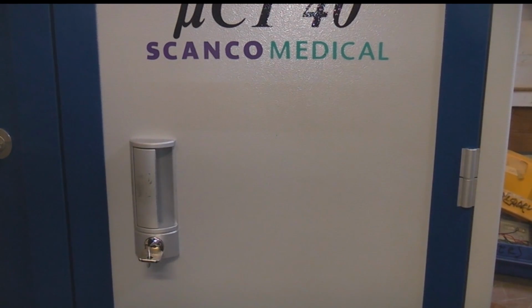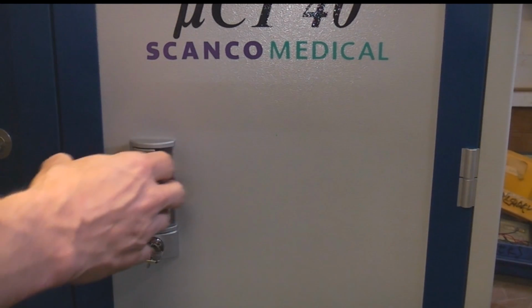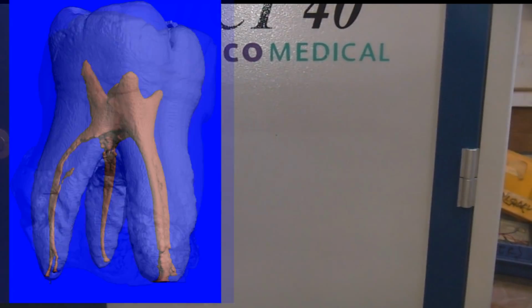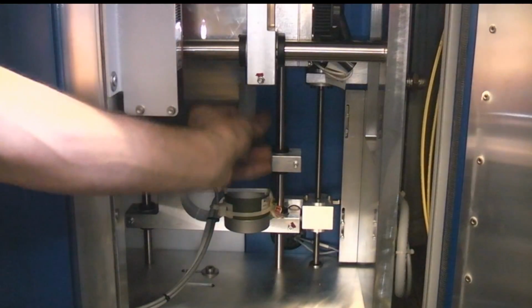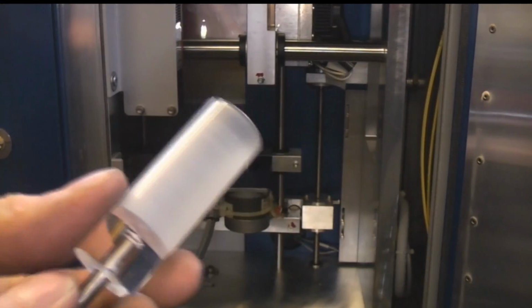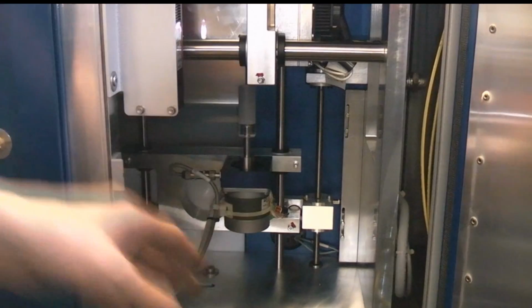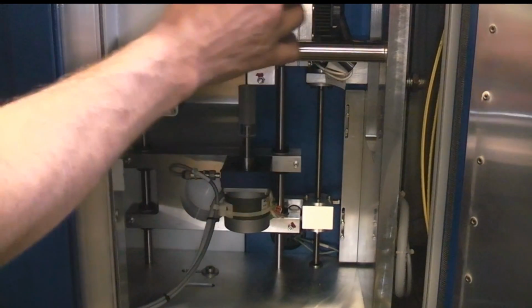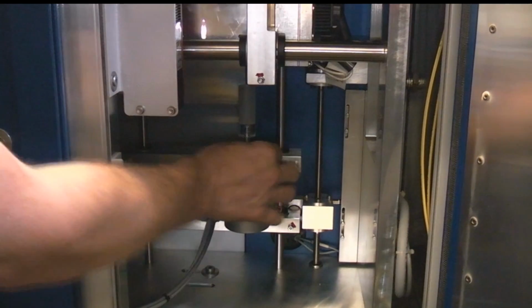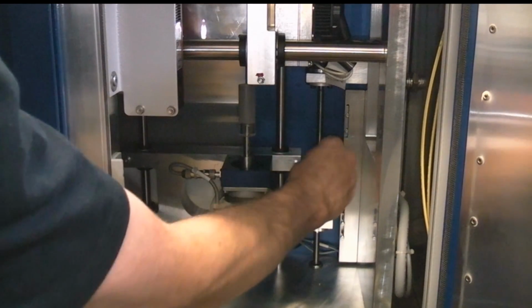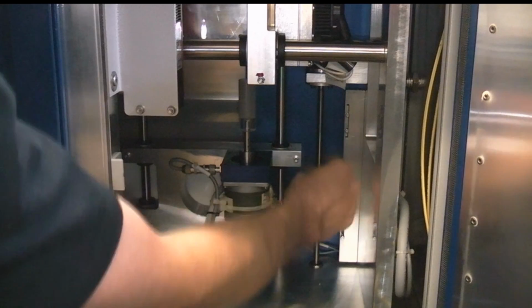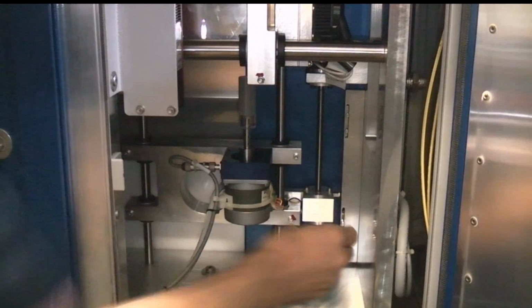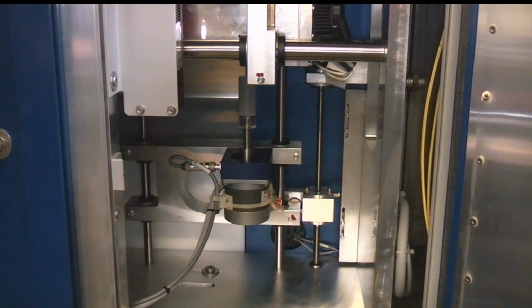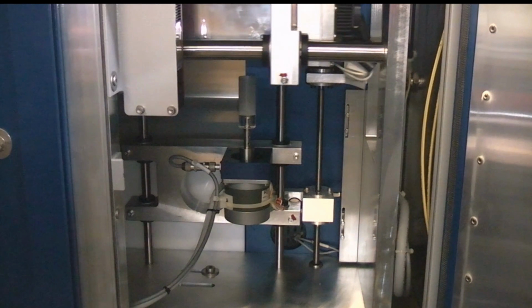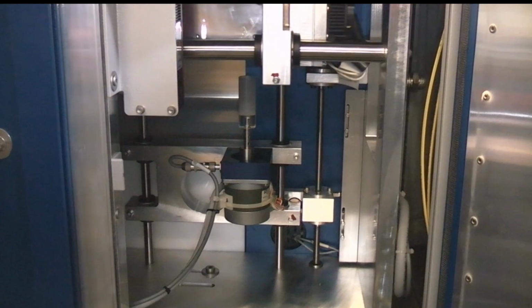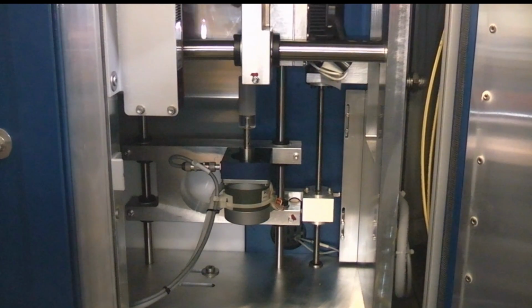This is aimed at medical applications and it was being used for scanning teeth and small parts of bone. Basically what we've got here, the sample goes in there, so obviously you can only scan very small objects. And basically this assembly moves up into the X-ray head here. It can be rotated in that direction. There's a lead screw, a very fine pitch, like a 1/2 mm pitch lead screw that moves it up and down here. I think there's probably another motor inside there because there's 4 motor control boards. I can't see where the 4th motor is. And there's this sort of basically slides across to provide another axis of movement.